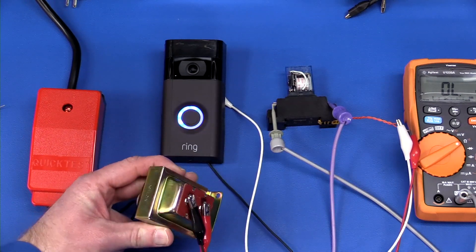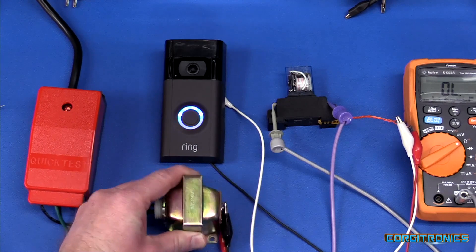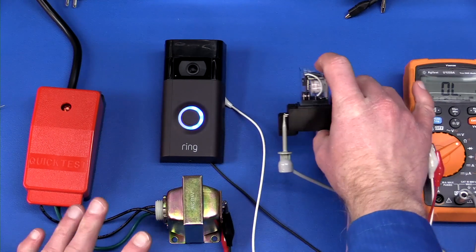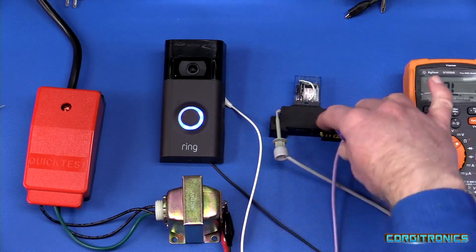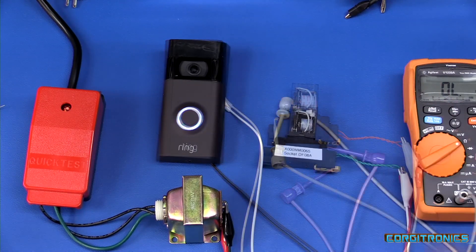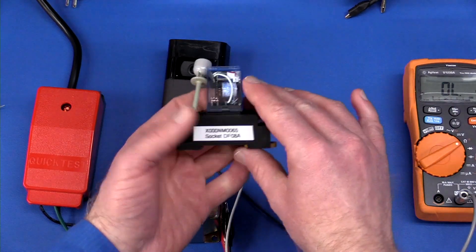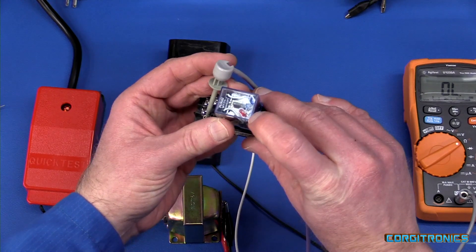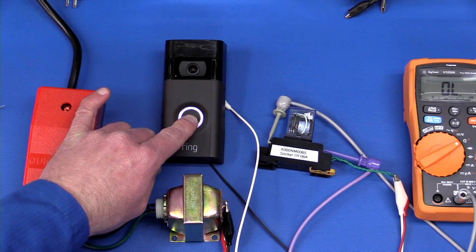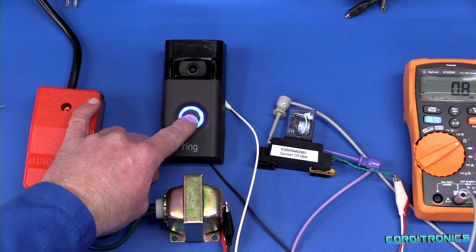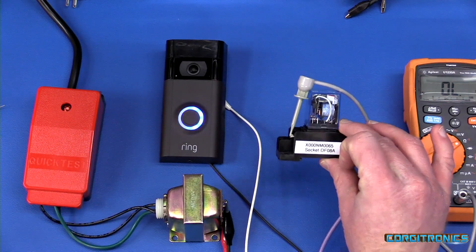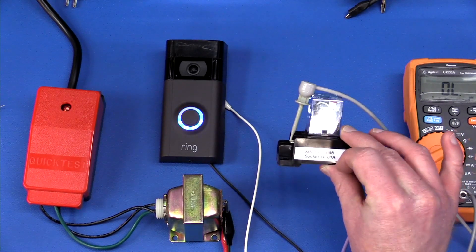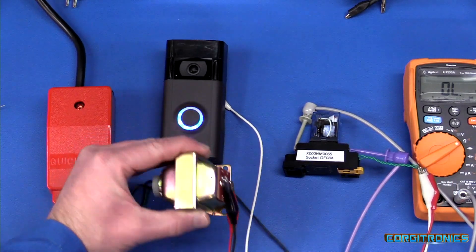Sure enough, a common cheap 16-volt builder grade AC transformer absolutely can trigger a 24-volt AC relay, assuming you get the right one. In fact, let's try one of the crappy ones. This relay was the one with the worst performance, the one with the green wires attached to it. And it has, of course, one of those red LED indicators here on the top. And contact. So even the worst relay still worked just fine. The worst 24-volt relay of our set of three worked fine on a builder's grade 10-watt transformer.